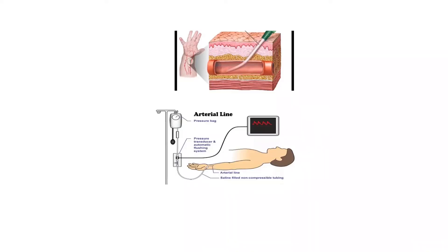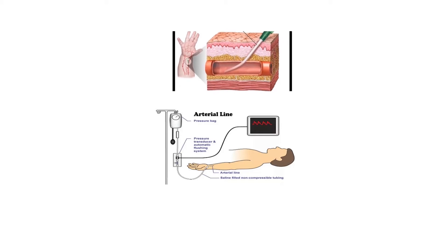As you can see here, we have a catheter going directly into the artery. This catheter is connected to a tubing system that contains a column of normal saline coming from a pressurized bag — pressurized to around 300 mmHg. The catheter detects the oscillations in blood pressure based on systole and diastole, and this pressure is picked up by the column of saline.